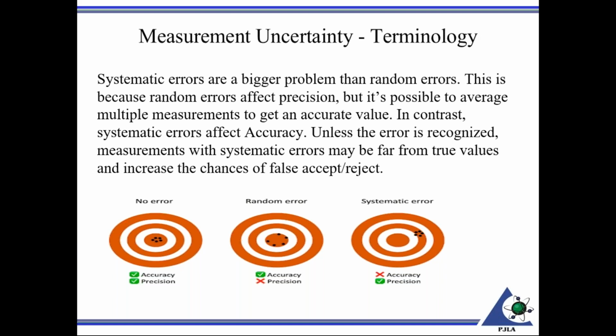the true value, or the middle there, as opposed to systematic, which is over there on the right, where we're hitting a mark. We're consistently hitting the mark. However, that could be the wrong mark. So regardless of how many more data points we collect, it's not going to offset the accuracy at all. We're not going to see it. We're just going to know that we're consistently hitting the mark, but it's not an accurate mark. So you have to look at that when you're looking at measurement uncertainties, including those in the budget or including them as a contributor.